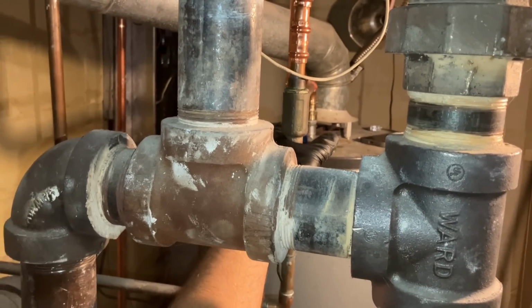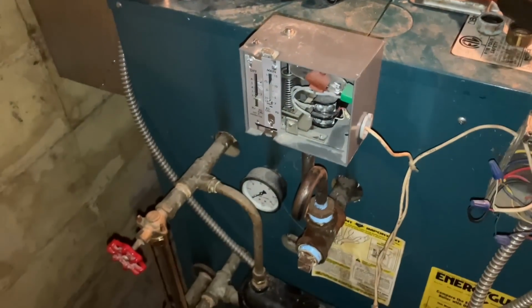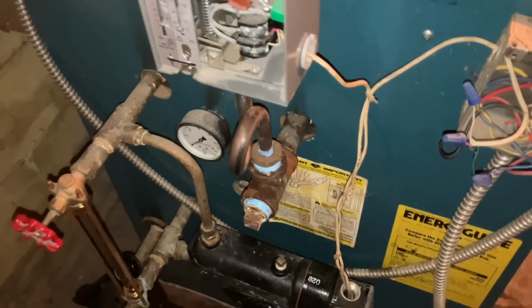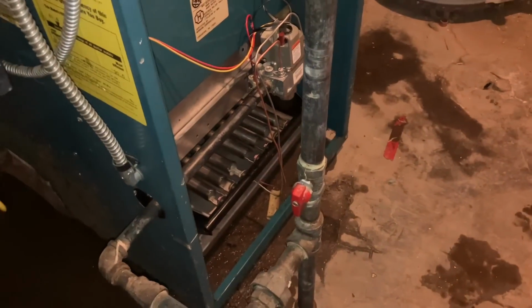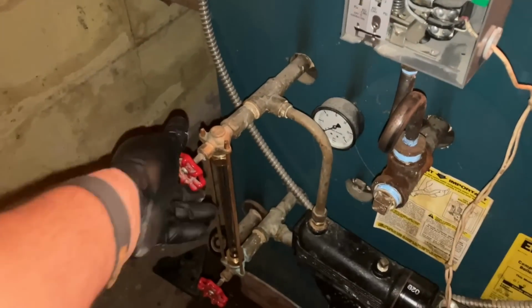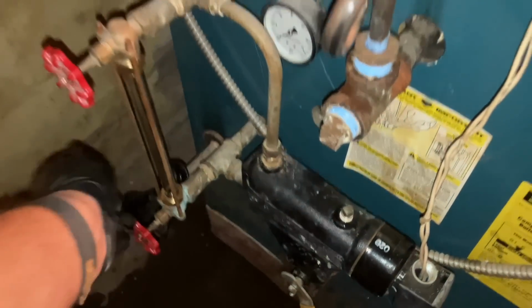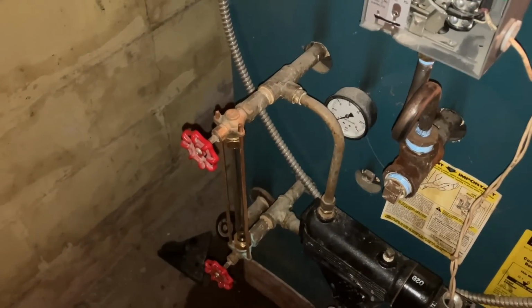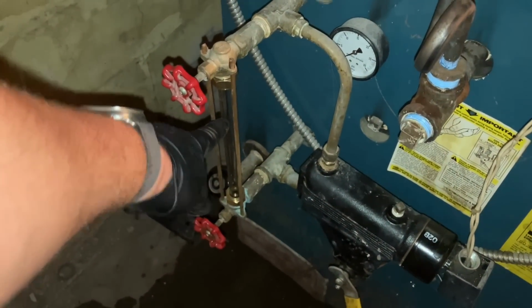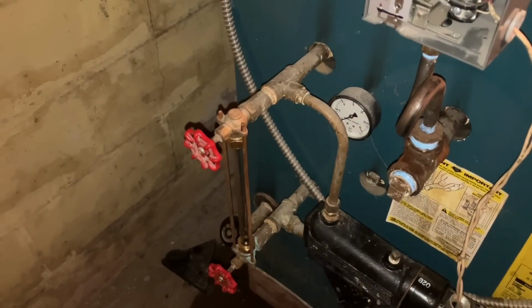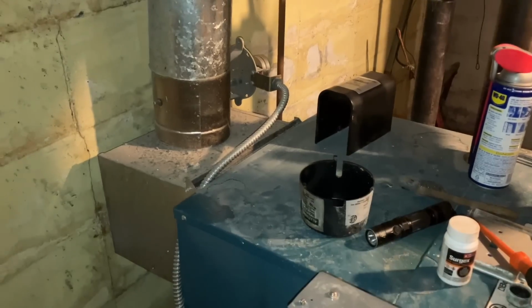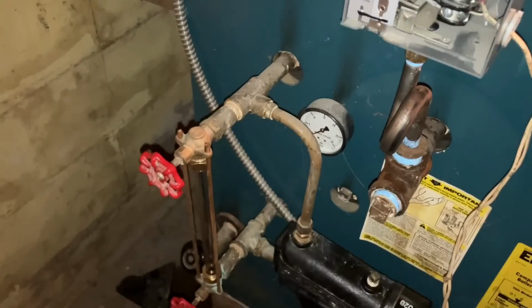Let's fill up the boiler manually. Now, if I suspected there was a compromised heat exchanger, and had evidence of that when I vacuumed out the combustion chamber, I would be filling this boiler to the top. But I don't suspect there's a problem with the heat exchanger, so we're going to fill this up to about three-quarters full on the sight glass and prepare our equipment to do a combustion and draft analysis. And while we're heating this boiler up and creating steam, we'll clean off the top of the boiler and make sure that everything is snug and tight.